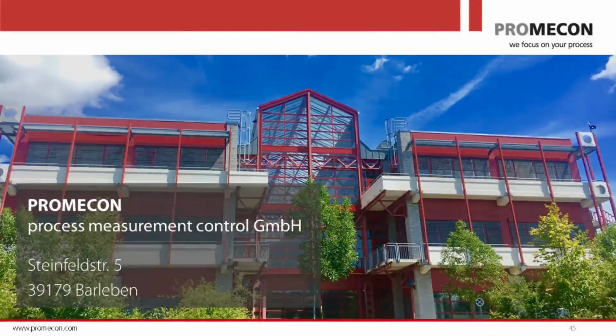I've seen boiler excursions, I think they're called, in other countries, not in the US, fortunately, but boiler explosions when you, for example, have very, very bad air staging, or you have even the fire going out and then come back on again. But these are catastrophic events. And usually in a well-maintained power station, even with the analog measurement technology, these should not happen, because you have CO control and you have feedback loops and you have a total O2 measurement.